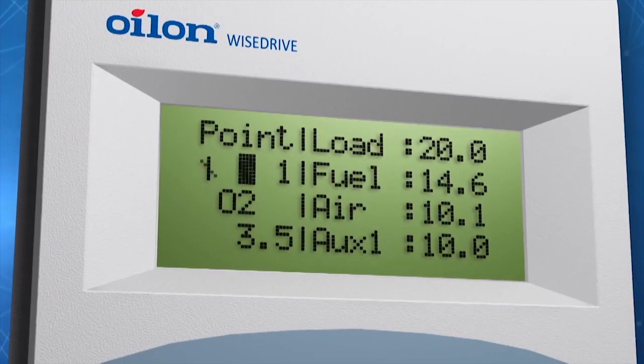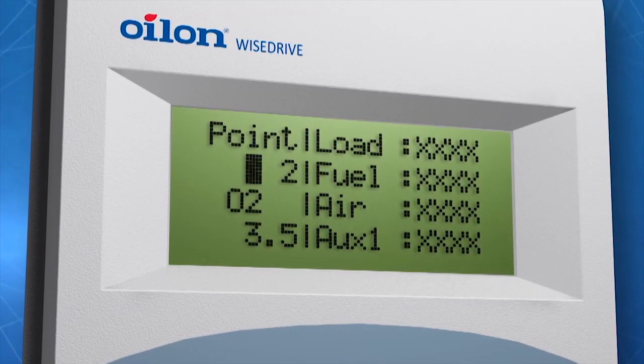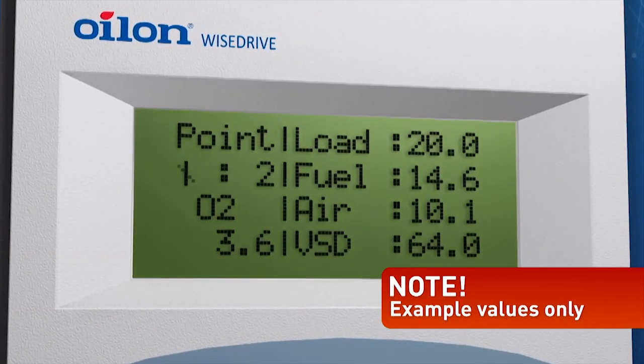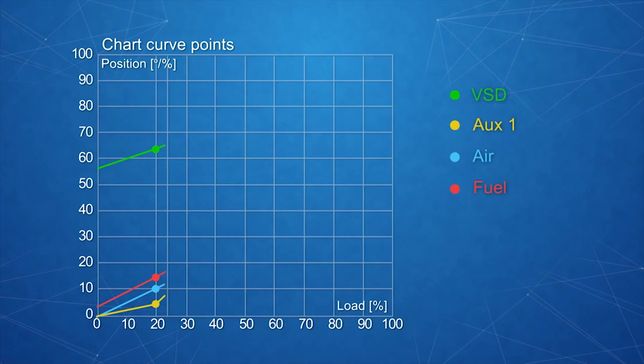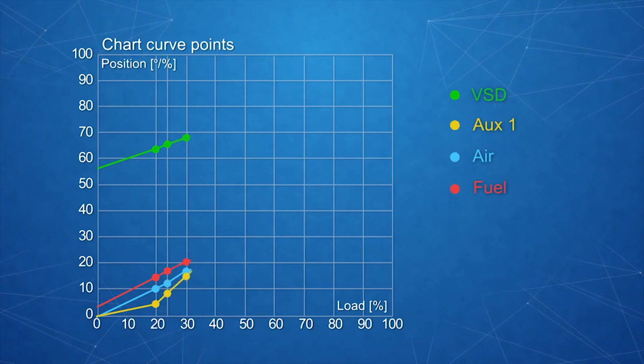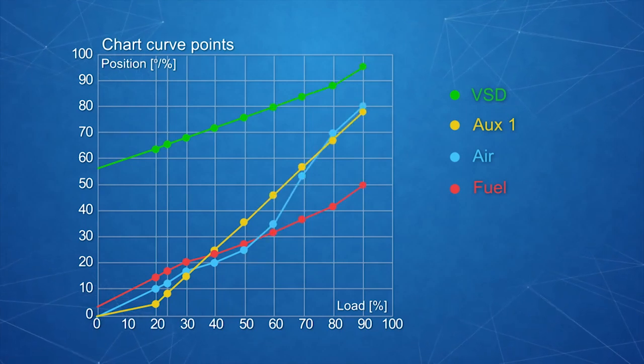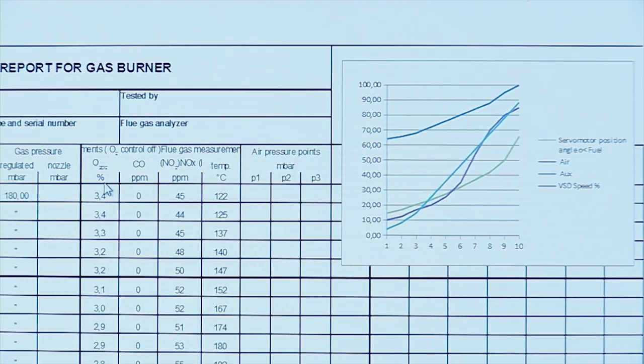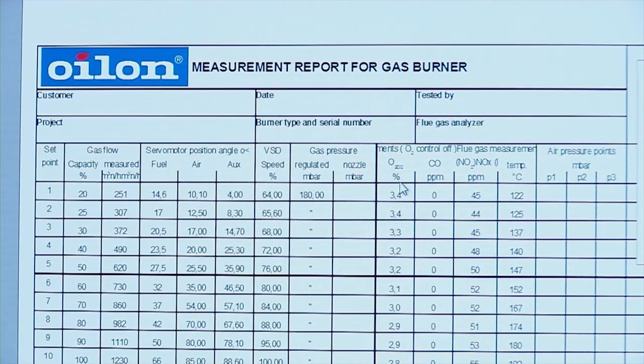Note that you can modify any point data at any time. Continue with the next points by adjusting the load manually and then adjusting the other values to match the actual values. You can create a maximum of 15 curve points. Normally it's enough to set 7 to 10 curve points, depending on the fuel. The ratio curve should be as smooth as possible. When all curve points have been created, save the whole parameter setup by pressing enter after exiting the menu. Remember to fill in the measurement report for the burner.